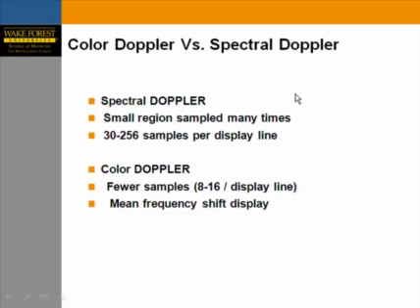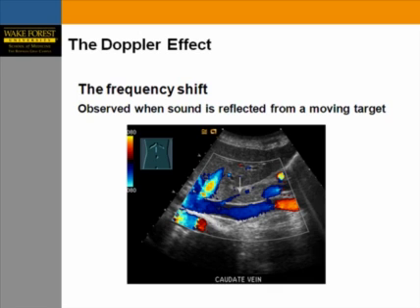Color Doppler versus spectral Doppler: spectral Doppler samples a small region many times, using about 30 to 256 samples per display line. Color Doppler uses fewer samples — 8 to 16 per display line — with a mean frequency shift display. The Doppler shift is the frequency shift phenomenon observed when sound is reflected from a moving target.